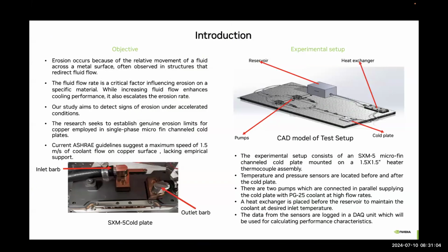So we are working on an erosion study for single phase. As you know, our rack densities are increasing tremendously, so we need higher flow rates and maybe more efficient cold plates if we stay with single phase cold plate cooling. We are already cooling around 150 kilowatts per rack, and future projections are much higher. So we started looking into an erosion study because in the literature it is given mostly as 1.5 meters per second for copper surfaces.